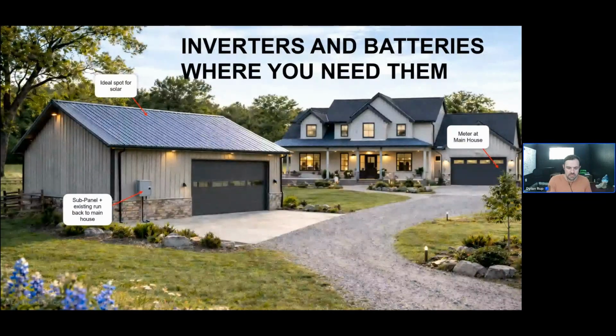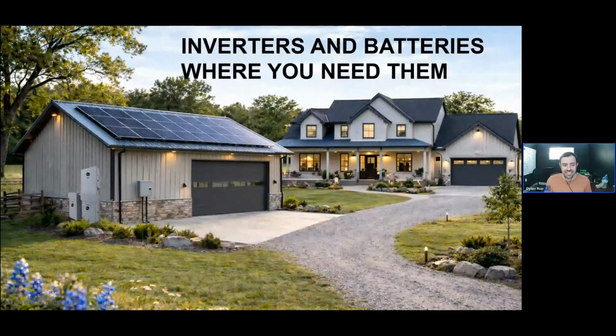Now, what you're going to see with our FlexBOSS line is that this situation can easily be handled by the solution set. So here we now see we've installed our solar on the roof. We have our FlexBOSS inverter and batteries where there's not going to be a significant DC run over to the inverter. So those have been installed right there on the shed or the garage, on a wall in some shade so they aren't subjected to direct sunlight. And then we're going to put the GridBOSS at the main house right next to the meter, right? Because the GridBOSS is the interconnection device, it is what actually enables that interconnection with the utility. And so it is usually the easiest to place it right next to the meter to minimize conductor runs, especially the large conductor runs that are necessary to carry the full service rating for the home.